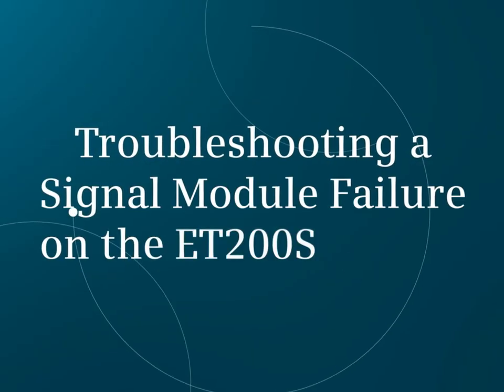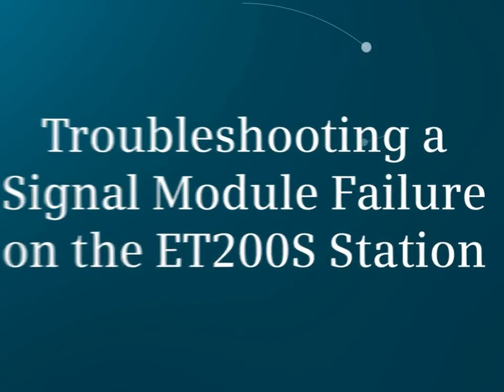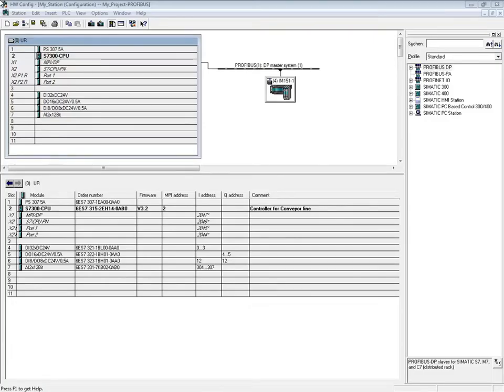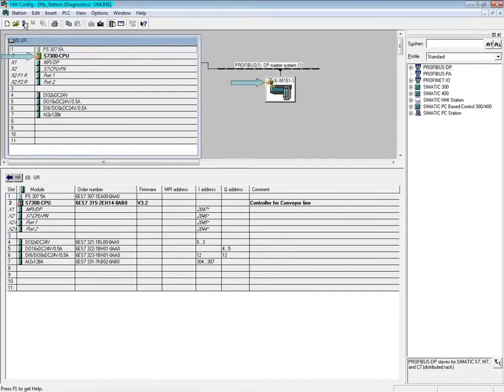Here you'll see how to troubleshoot a signal module failure on the ET200S station. Placing the hardware configuration online gives you a nice graphical view of the system and helps to identify where problems exist. Click the Online button. There's a fault mark on the CPU and on the interface module IM151-1 of the ET200S family.